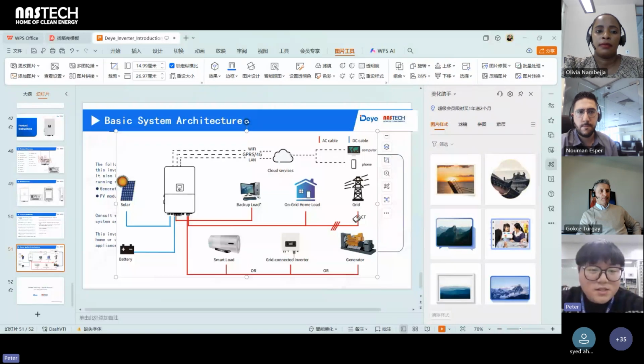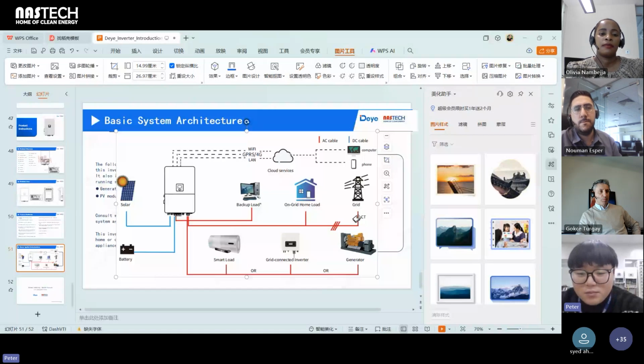He mean that for PCS system, right? I think, well, it's not clear, so maybe we... If it's for PCS system, it's also that we will have a different circuit breaker on different load output of the PCS, because the power is very high. You cannot just use one breaker for all the backup. We will have separate breakers on separate load output.